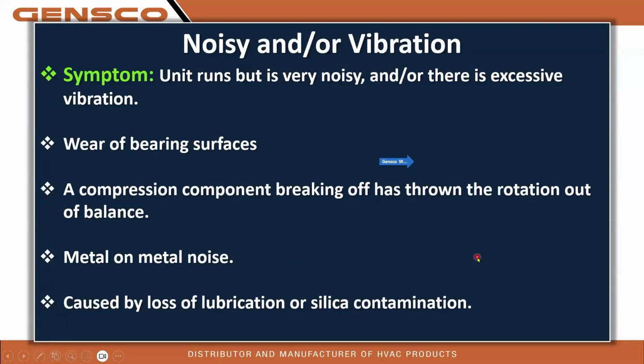Another failure, the more subtle type, would be a noisy compressor or one that is vibrating badly. The unit runs, but it's either very noisy or it vibrates a lot. It's due to wear of bearing surfaces, or a compression component has broken off and has thrown the rotation out of balance. Metal on metal noise may be present, caused by a loss of lubrication or silica contamination.